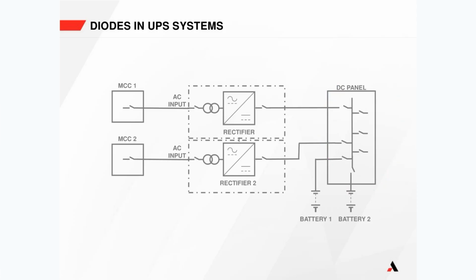Now there are inherent properties with that. Hopefully I won't overcomplicate this, but whenever you have a charger, the charger always has to look at its output voltage. It uses feedback. Most 60-cell lead acid systems, the float voltage is 135 volts DC. So what the charger does is it has a wire going to the output of the system, and it says, okay, am I at 135 volts DC?